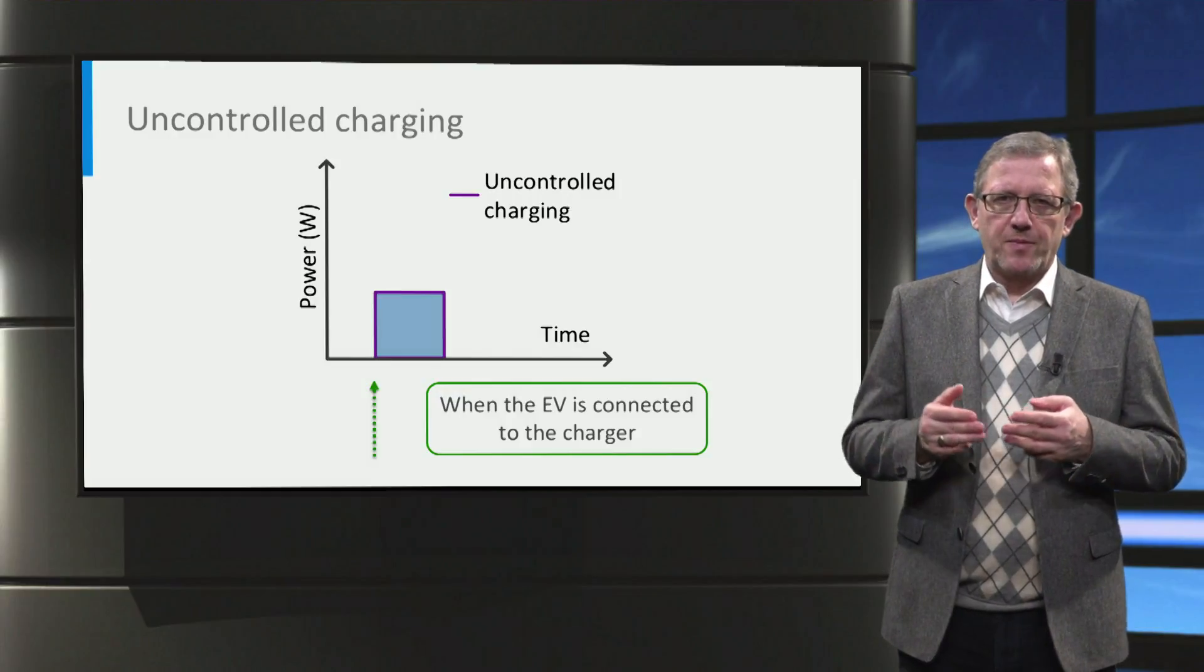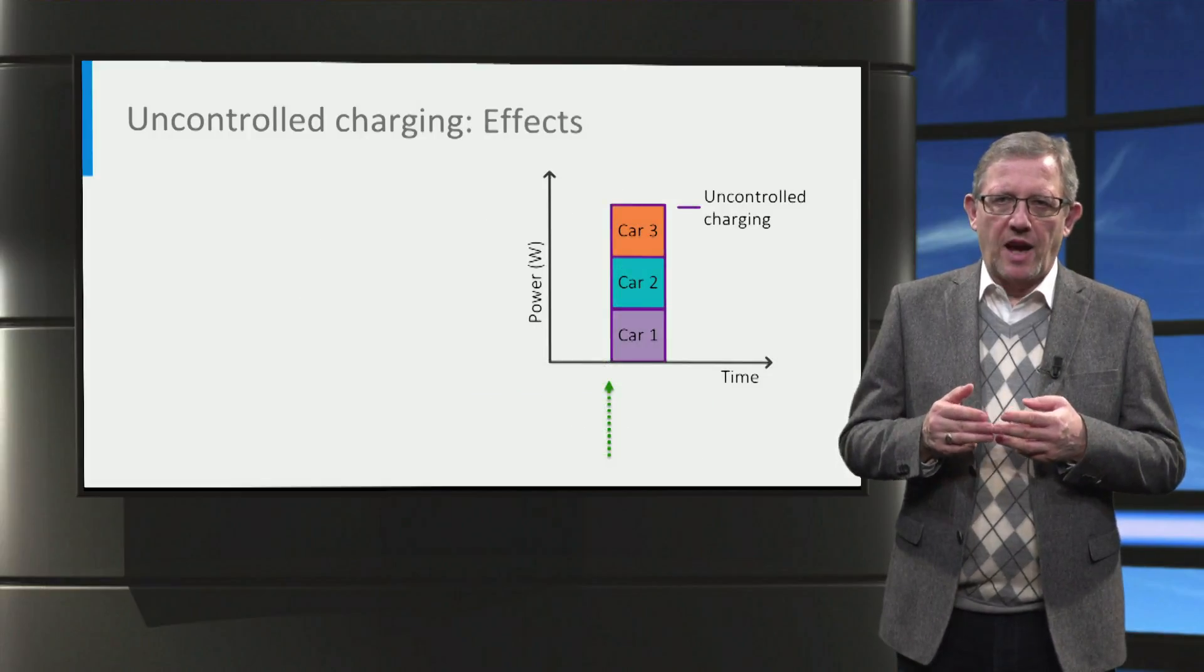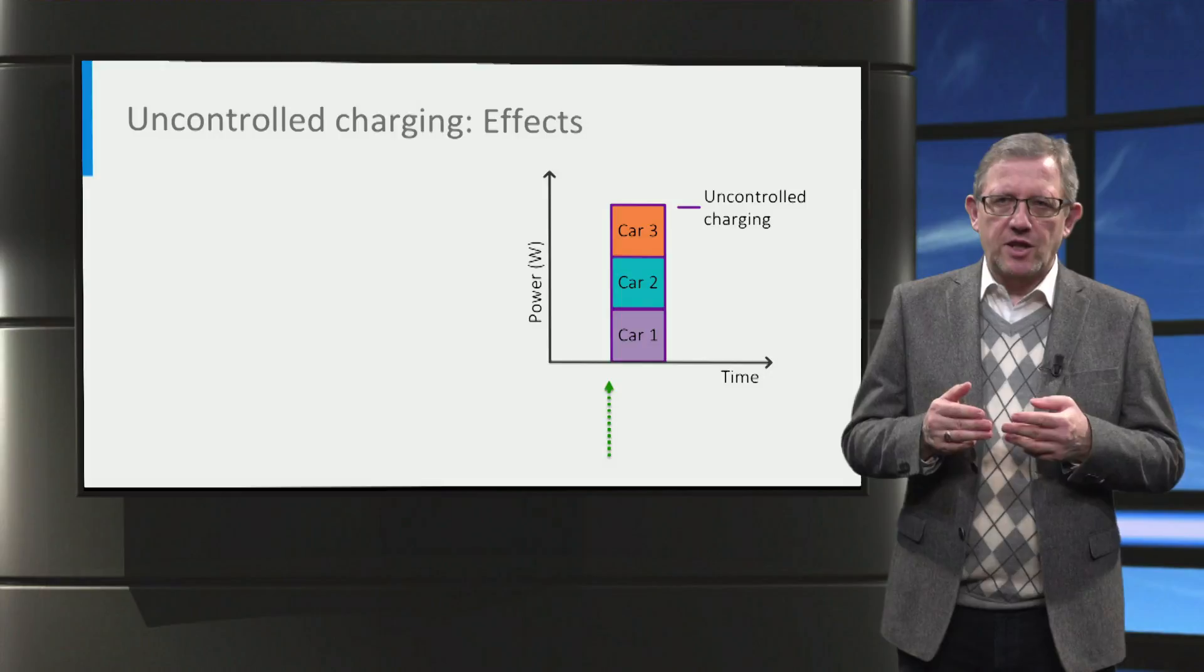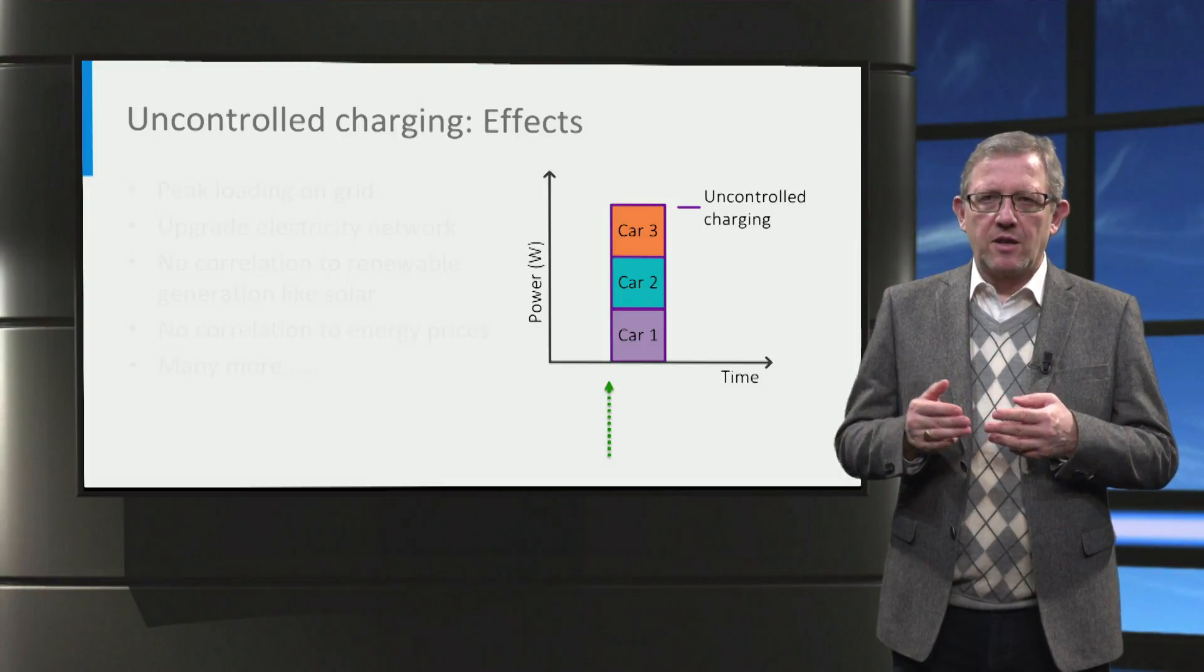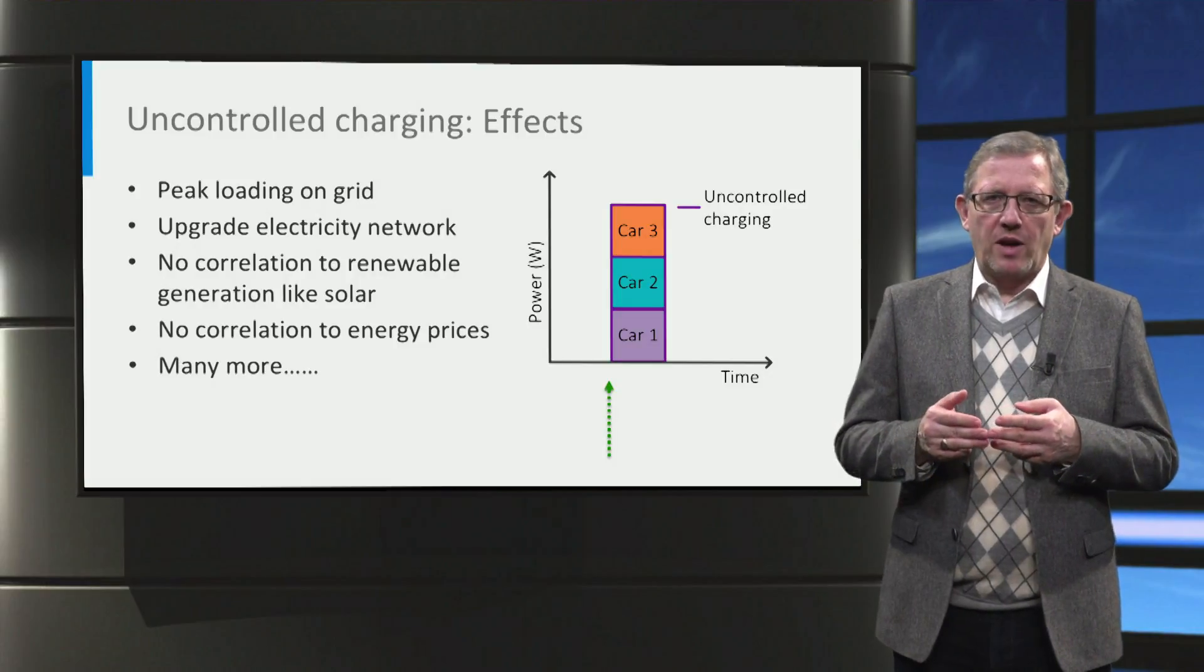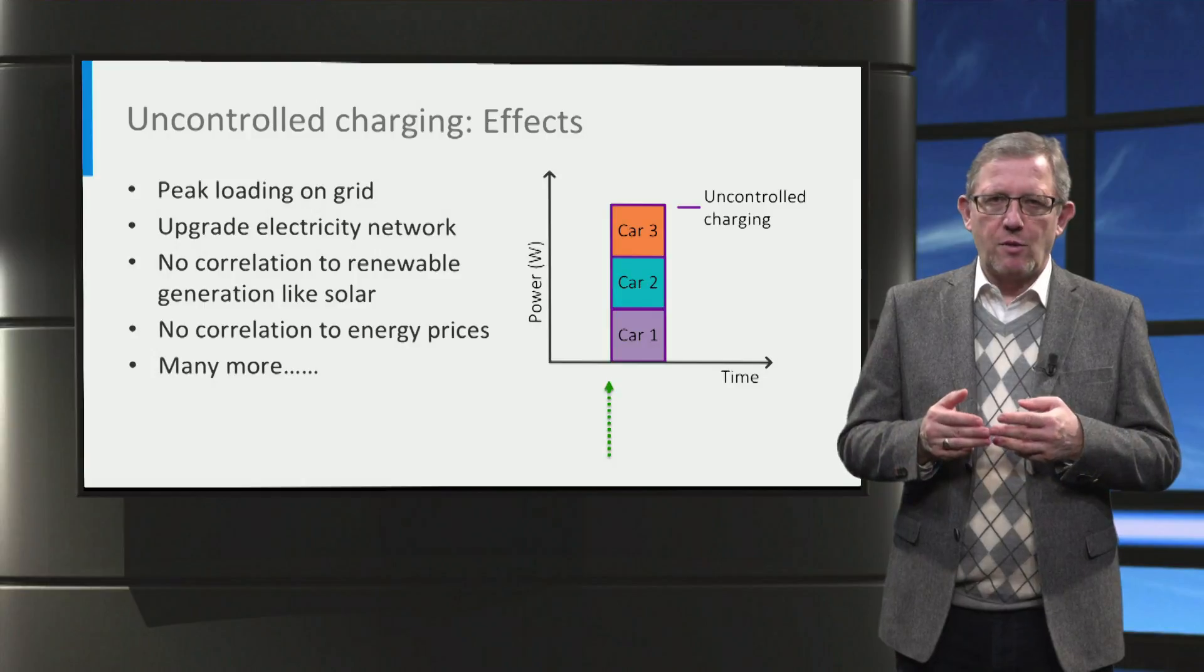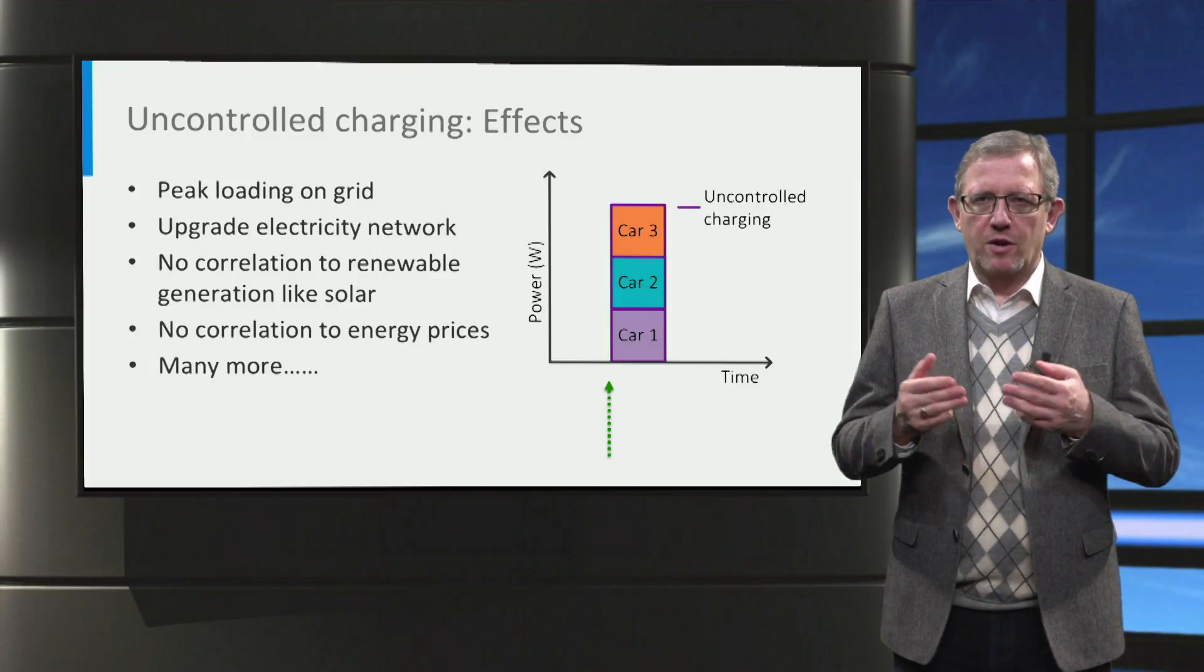Now what is the disadvantage of this? In the case of multiple cars connected at the same time, then all the cars will charge at the same time when they are plugged in. This may lead to a peak loading on the electricity grid. If the peak is too high, then power lines and transformers in distribution network will have to be upgraded. So more cables, more transformers.